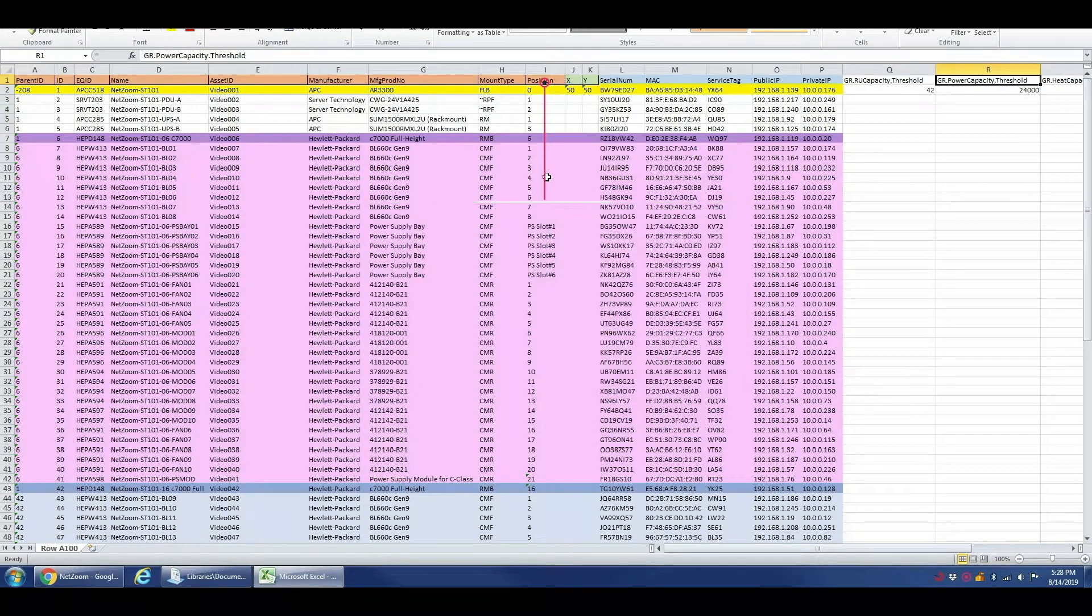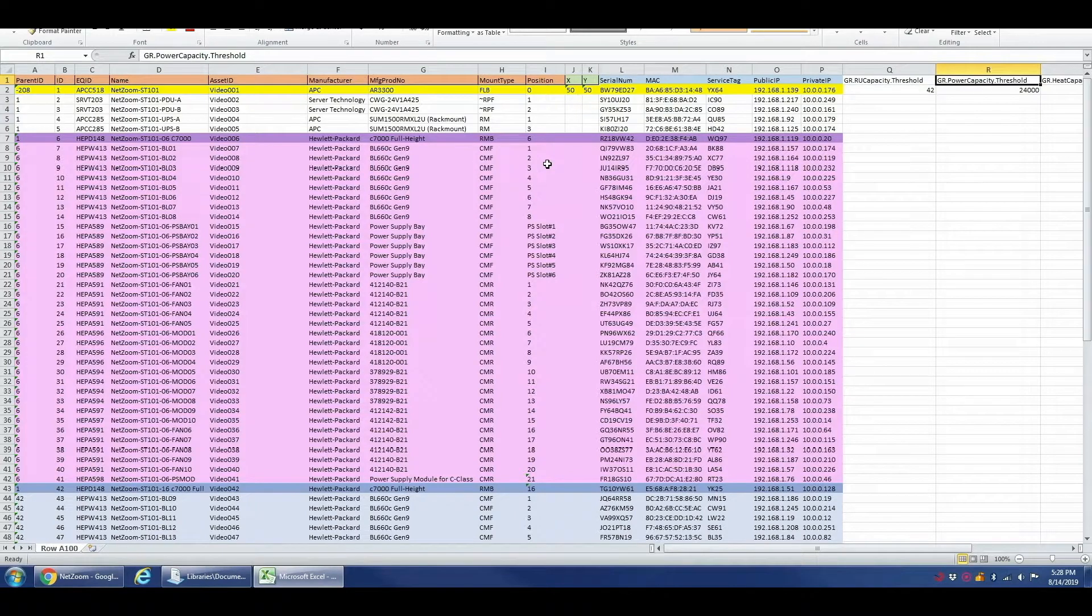The position refers to the position of the rack or device. For racks on the floor, you would use zero. For any device mounted within a rack, rack unit, you would use the number of that rack unit. And for any module mounted within the slot of a device, you would use the slot number on that device.